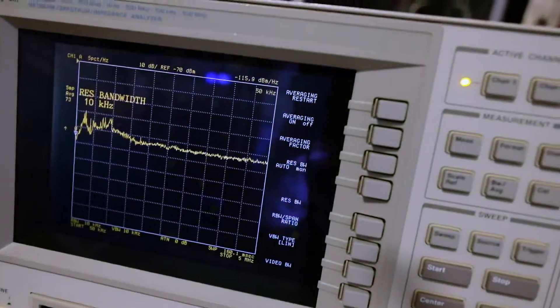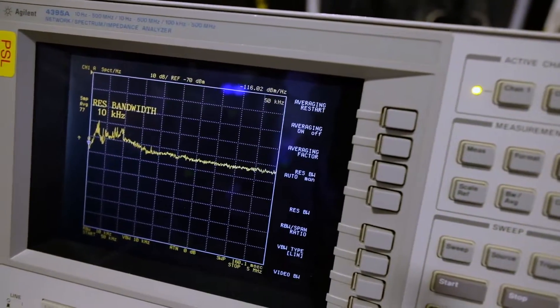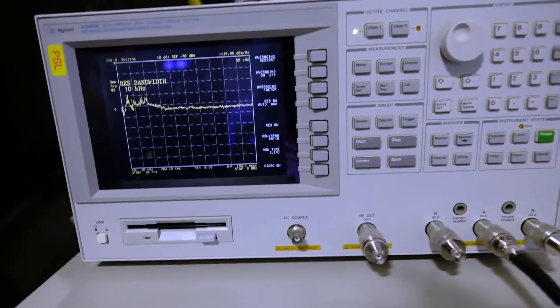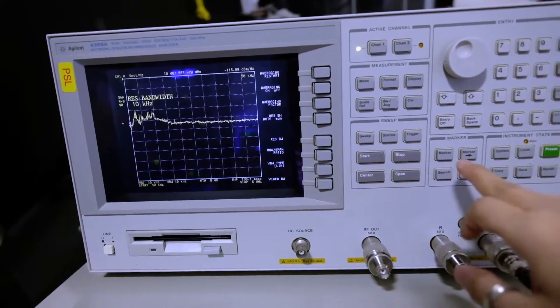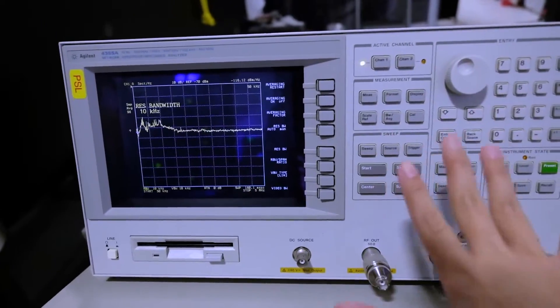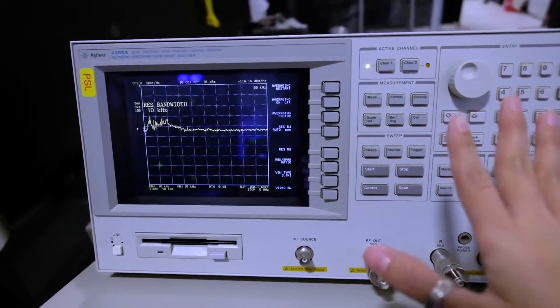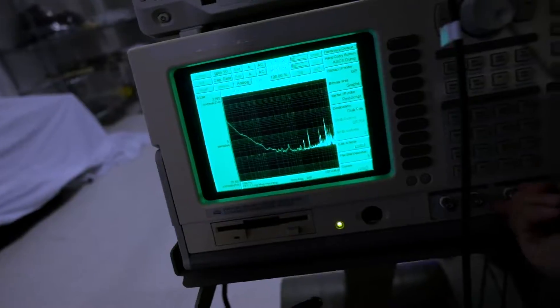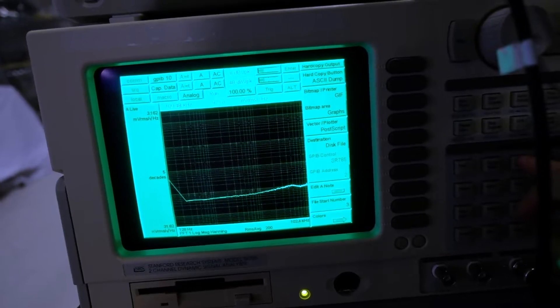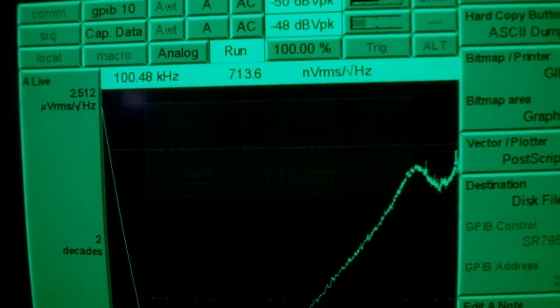So I have just saved my volt per hertz measurement. Here I'm going to also get my dbm per hertz measurement and see how that compares. They should be the same. They should have the exact same offset from the SR785 once converted into a proper unit. I'm going to also take a SR785 data. I need data. Volt per hertz. It's what I want so that we can compare how far off the Agilent is. Boom. Done.